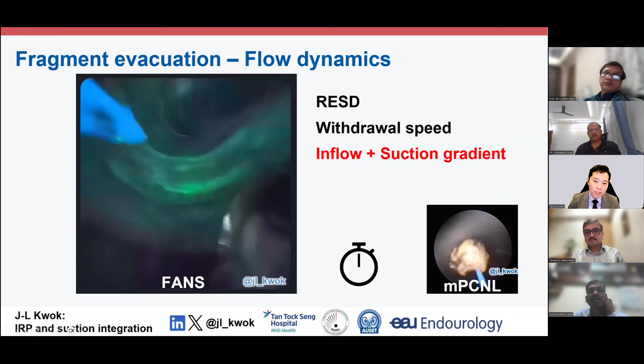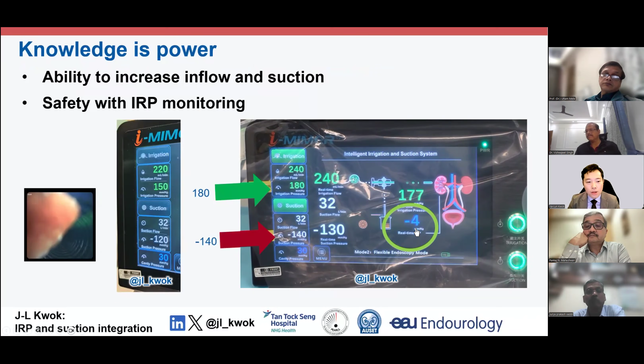And with the IRP, knowledge is power, and I think you're able to increase inflow and suction in line with what I said, because you are trusting that the IRP is measured. So for example, on the left side, my usual pressure settings are 150 in, negative 120 out. In this case, the fragments were coming out very nicely. So I increased it to 180 in and negative 140 out. But with that, the machine actually auto-regulates to -4 to 0. And that allows me to trust my machine and go to higher settings to increase the efficiency of my procedure, yet being safe.